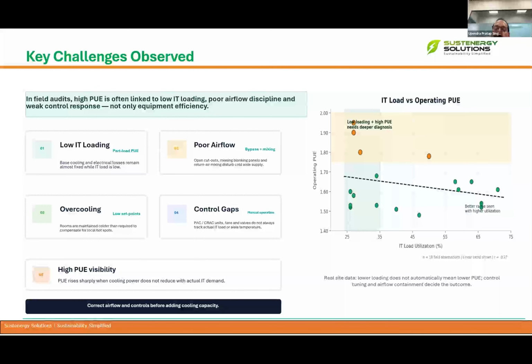And when we do the actual measurements on site, we find that at some places there is overcooling, and at some places there is undercooling. So that also we need to check and maintain, because mostly people install one or two sensors in the server room, and then they check the temperature and accordingly switch on, switch off the ACs or PACs, whatever cooling units are there. That is not the correct way. You need to check the temperature at the rack inlet. What is the actual air temperature going into the racks? There we will actually come to know whether our temperature settings are perfect or not. So we need to check that periodically and maintain it.